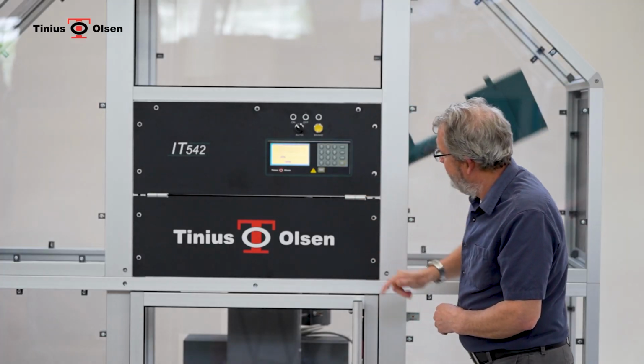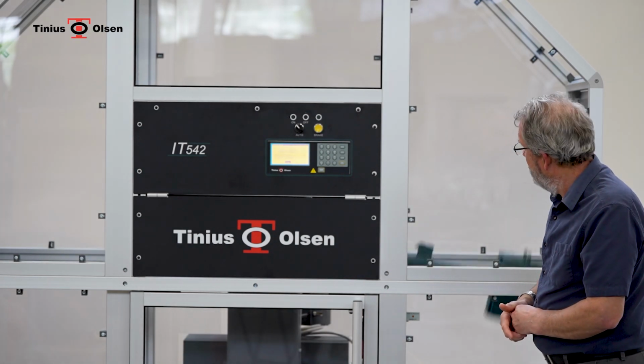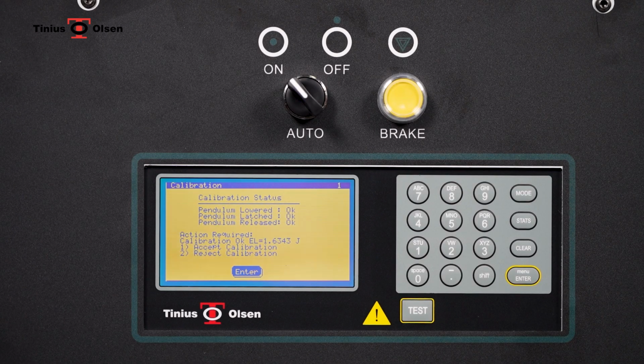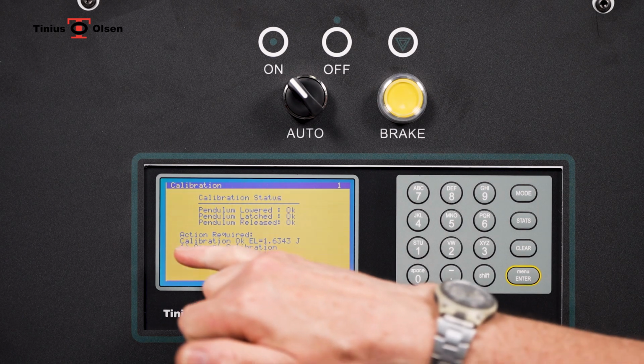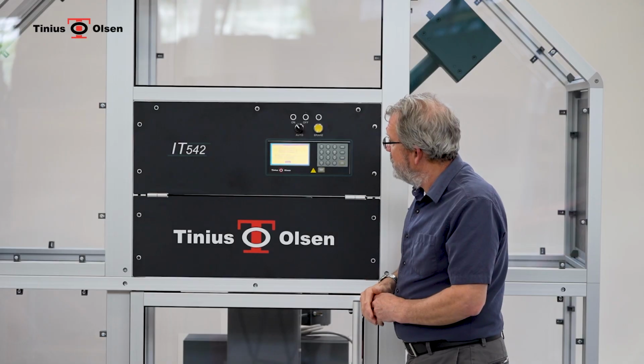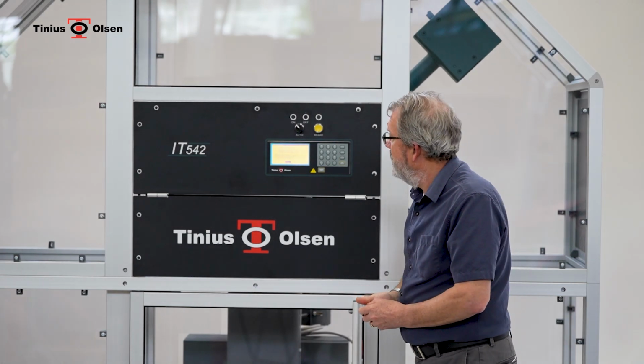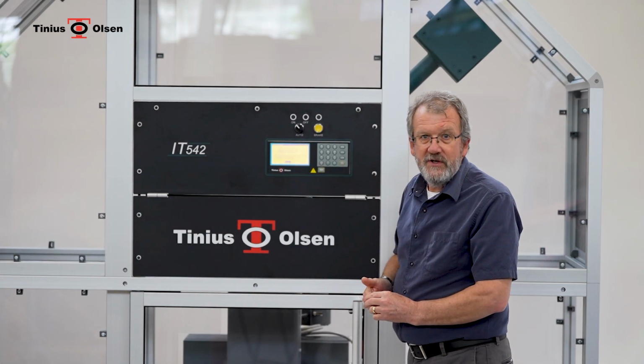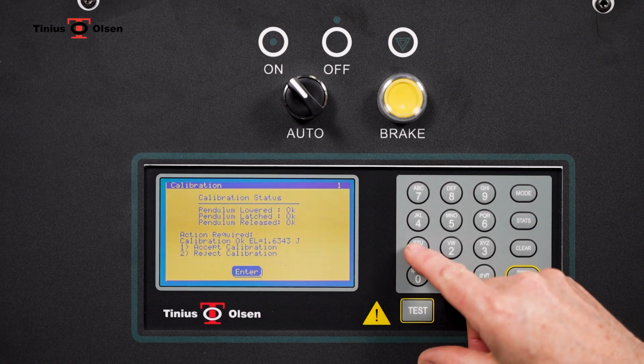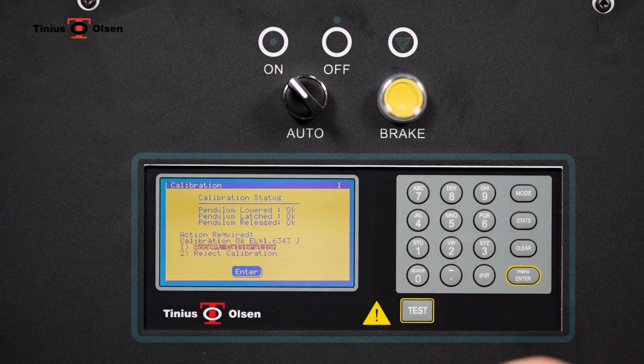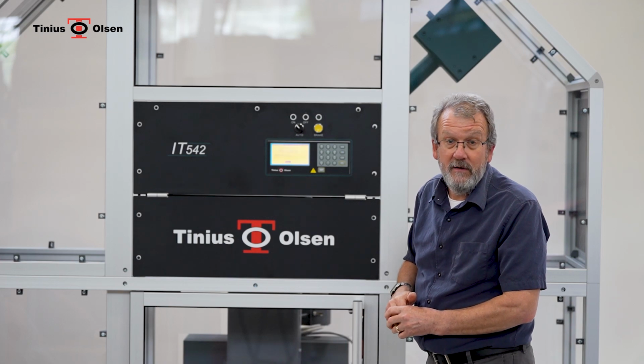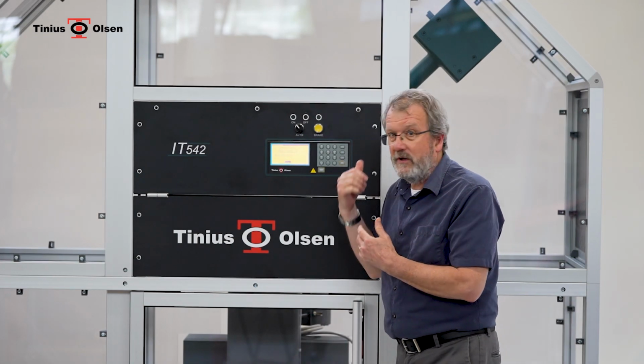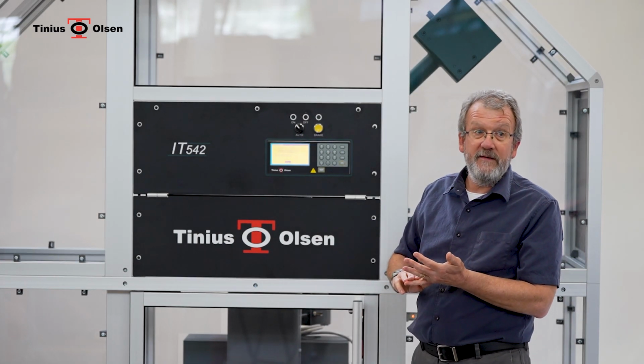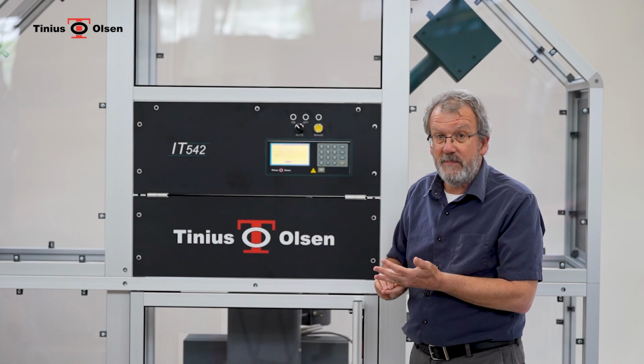Pressing the test button releases the pendulum and relatches it. It then shows us the calibration OK, energy loss is 1.2 foot-pounds, and we can either accept or reject that calibration. Upon acceptance, that value has been stored and all subsequent swings will be compensated by that value. A calibration should be performed on the machine every day or if there's ever a suspicious or suspect value taken.